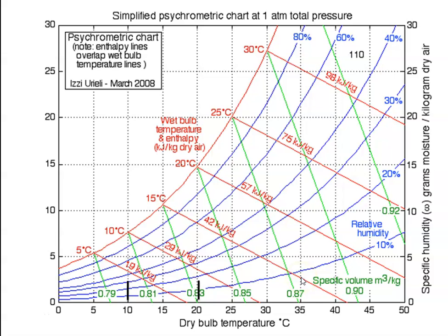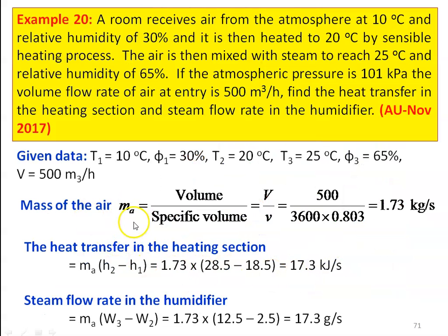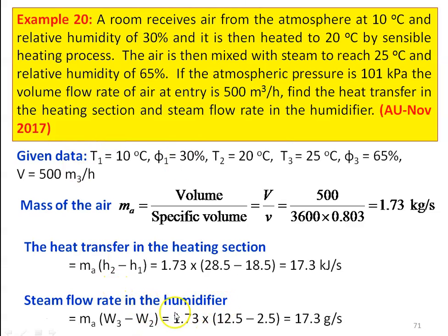Mass of air equal to volume divided by specific volume equal to 500 divided by (3600 × 0.803) equal to 0.173 kilograms per second. Heat transfer in the heating section equal to Ma × (H2 minus H1) equal to 0.173 × (28.5 minus 18.5) equal to 1.73 kilojoules per second. The steam flow rate in the humidifier equal to Ma × (W3 minus W2) equal to 0.173 × (12.5 minus 2.5) equal to 1.73 grams per second. These are the answers to the problem.